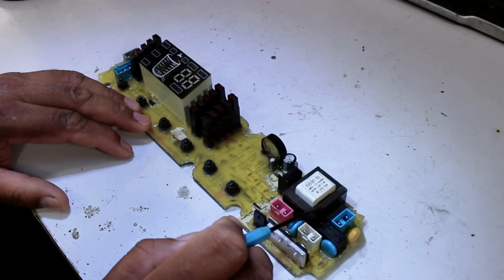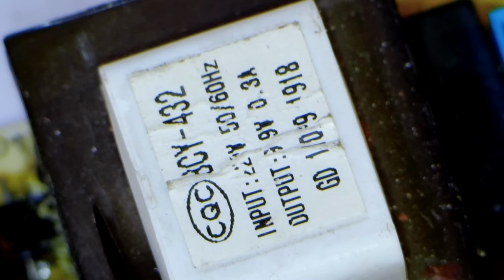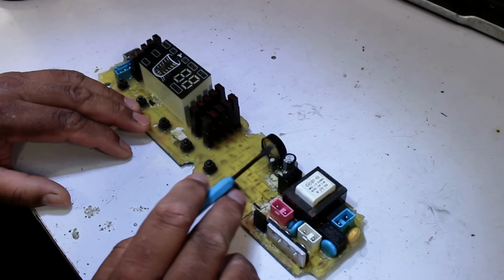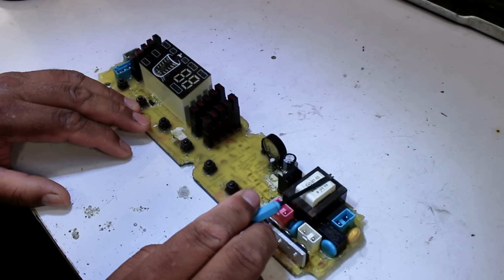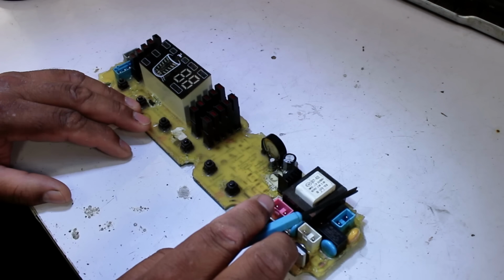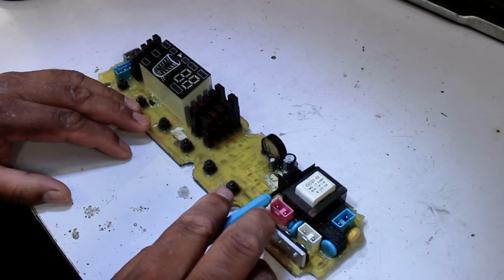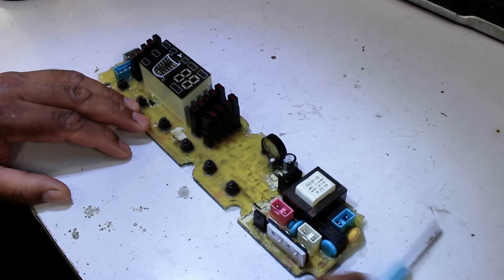The first thing to understand is that this PCB is transformer-based; SMPS has not been used in it. So the first test, if the PCB is completely dead, is of the transformer. It is necessary to check it, because if its high side is dead, the low side will never be able to generate voltage. So first we check it.